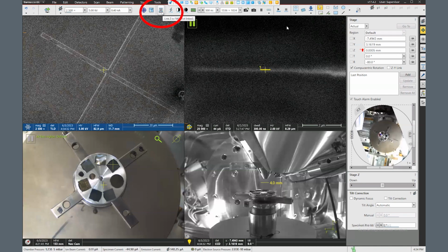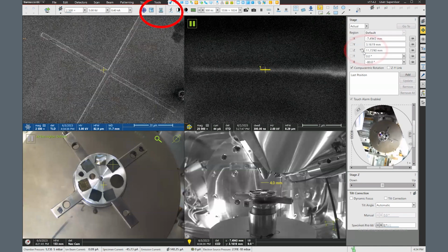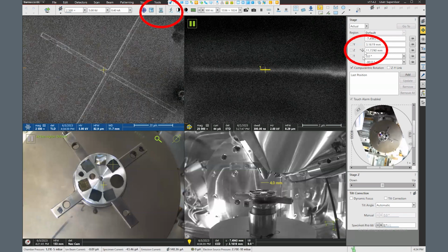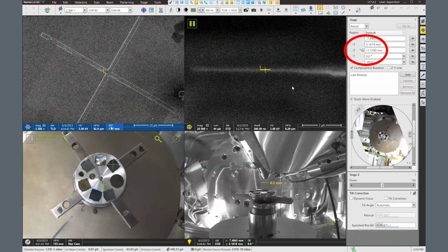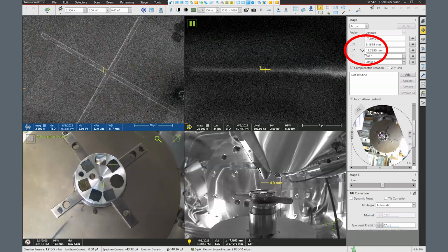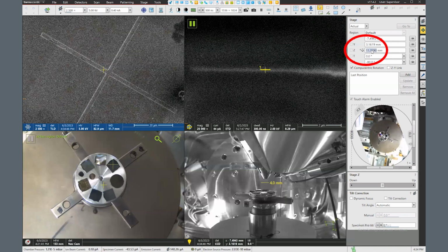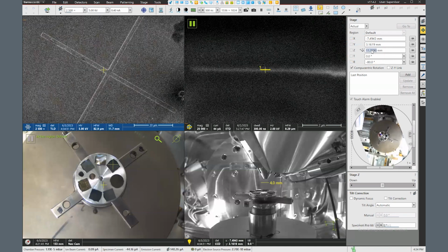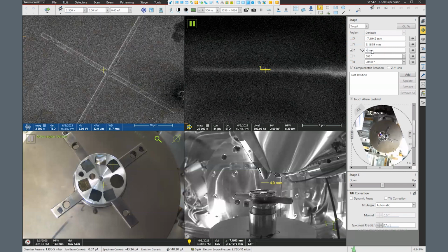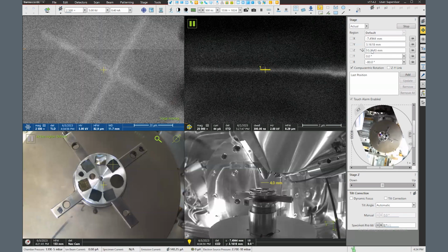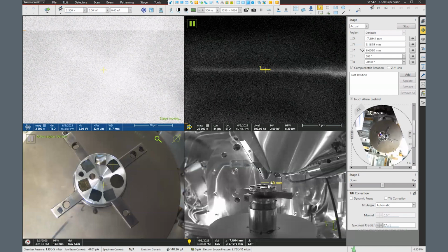So when I click that, you will notice that my Z, the red arrow, is gone, now replaced by a gray arrow pointing downwards. And the measurement more or less matches up with the working distance. So now I can put in my appropriate operating height, 4 millimeters. I can say enter. And I'm going to rest my finger on the escape key just in case it looks like I'm about to hit something. Shouldn't have to, but it's always a good idea.